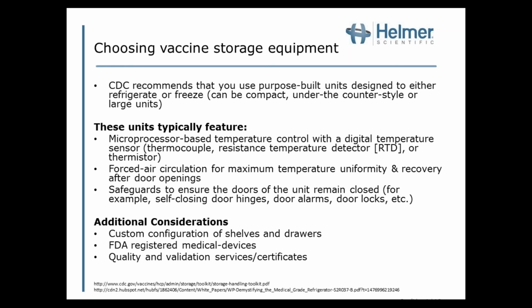These units typically also have safeguards to ensure the door remains closed, and that's a really important feature. To tell you a story about something I went through — I was filling in at a pharmacy location that had a standalone freezer unit, but it was a household unit, and it didn't have self-closing door hinges or an alarm or anything.